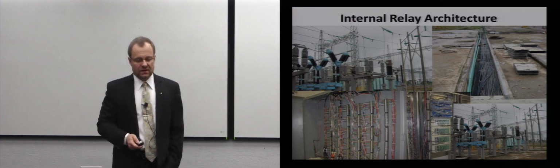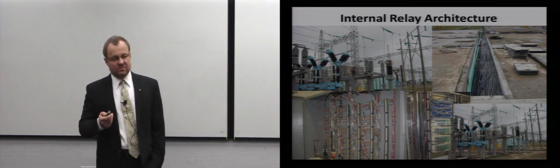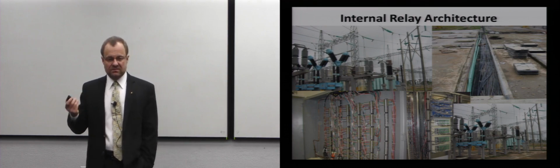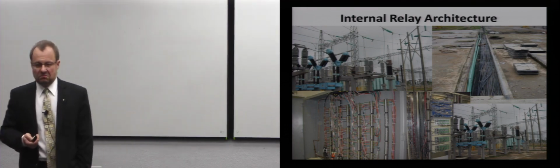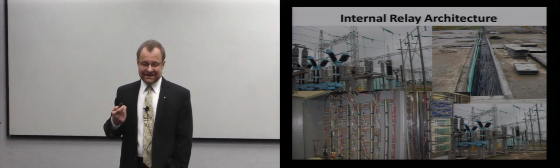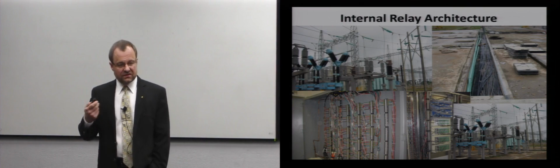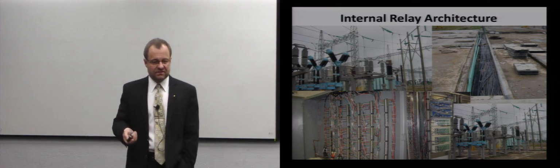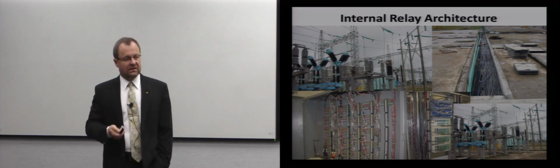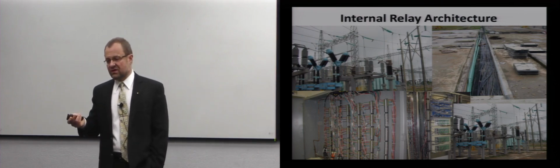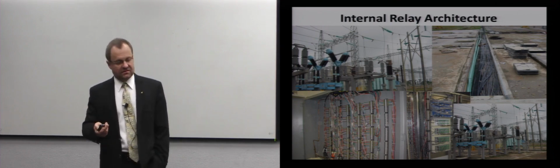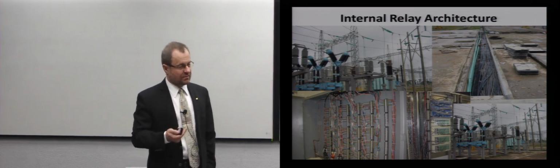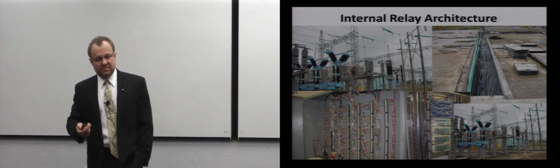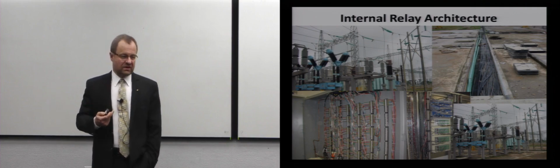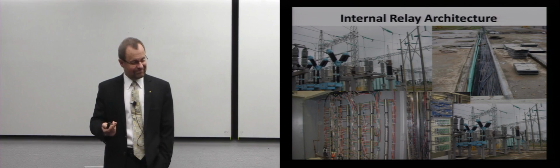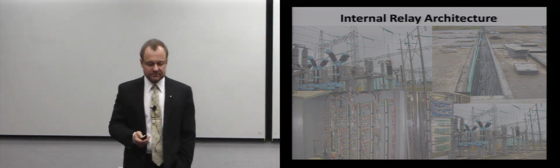Now, the reason I'm showing this picture is that you have to remember this is a dirty environment. And what I mean by that is not physical mud or something like that. It's electromagnetic interference. You have conductors that carry thousands of amps of current. You have a 500 kilovolt network. You have tons of coupling. You walk there with off-the-shelf equipment such as a video camera, and the damn thing will reboot on you, right? Because it's not meant to deal with this environment. We are building relays using microprocessors. New microprocessors run on 1.2 volts, and we are putting them in this environment, right? So we have to be mindful.